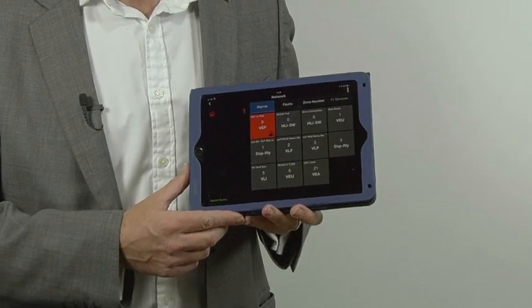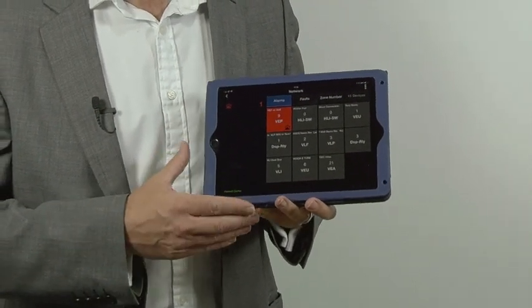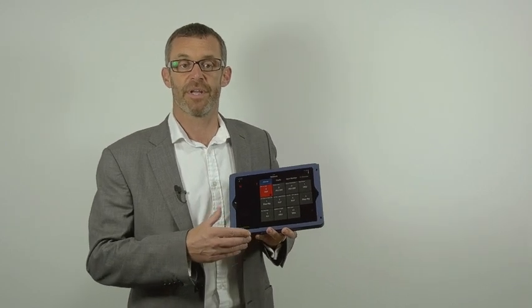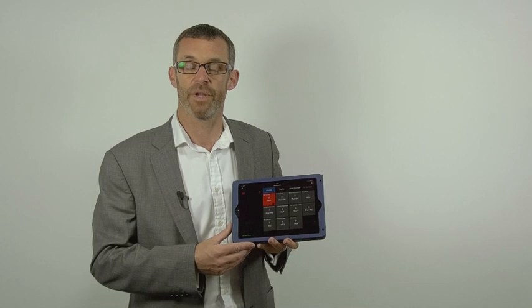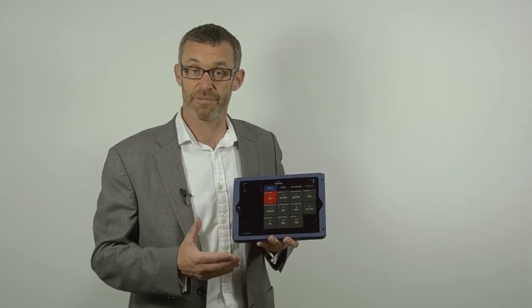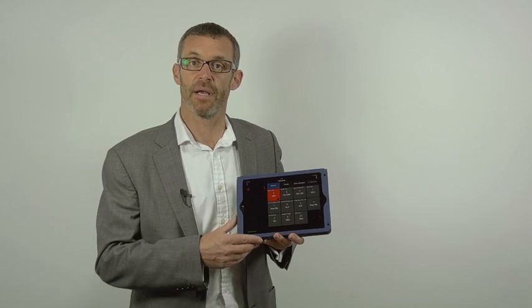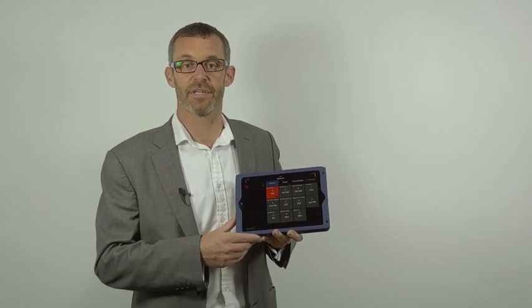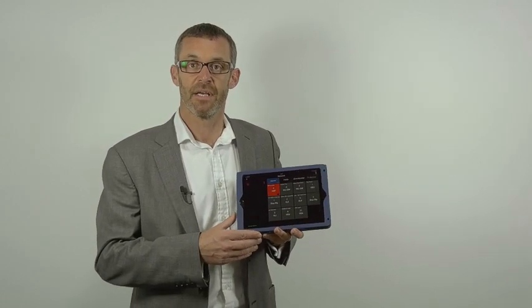The beauty of iVesda is that even though it's designed for the Vesda e-range, because Vesda e is backwards compatible, we can have networks with both Vesda e products and the laser-based product range all on one network using iVesda. This allows us to get information centrally for facilities managers or people reacting to the Vesda.